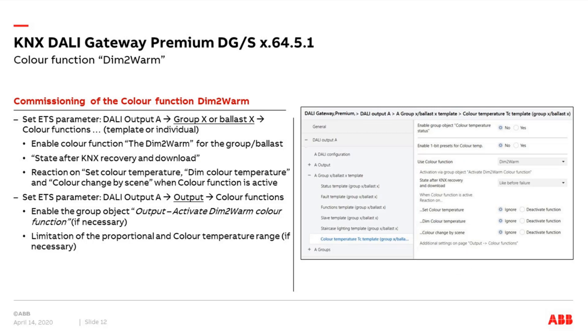Now let's look at the ETS parameters. First, we set parameters in DALI output A or B, in the group or in the ballast — using a template or individual settings. We must enable the color function Dim2Warm for the group or ballast, set the state parameter for KNX voltage recovery or after download, and configure the reaction when the DALI gateway receives a color temperature command, a dim command, or a scene call.